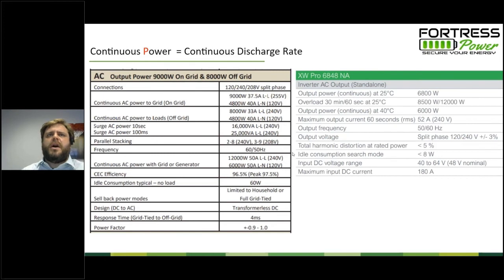So here are some spec sheets on a couple of different battery inverters, and let's just take a quick review to see what we have here. So here we have a battery inverter that says it's a 9 kilowatt battery inverter, and then it runs in an 8 kilowatt mode off grid. So the battery is actually capable of supplying a little bit more in a grid tied mode than in an off grid mode. And we would say, okay, when we are putting devices onto this particular brand of inverter, if we put more than 8 kilowatts of load onto an 8 kilowatt inverter, what'll happen?